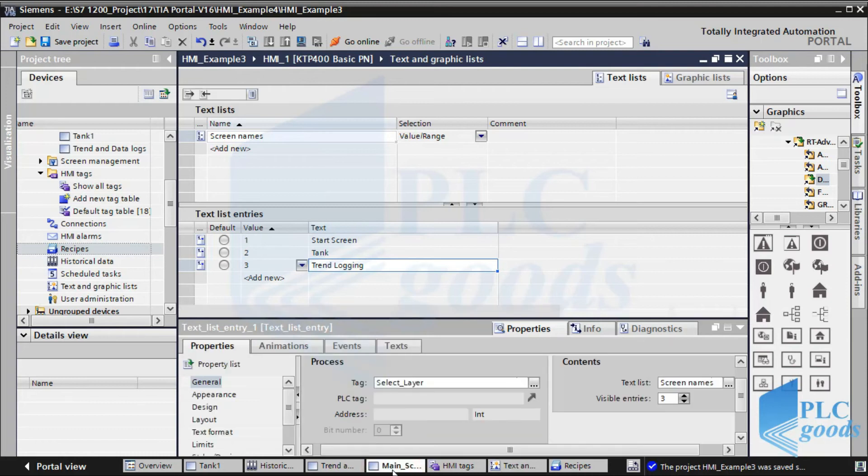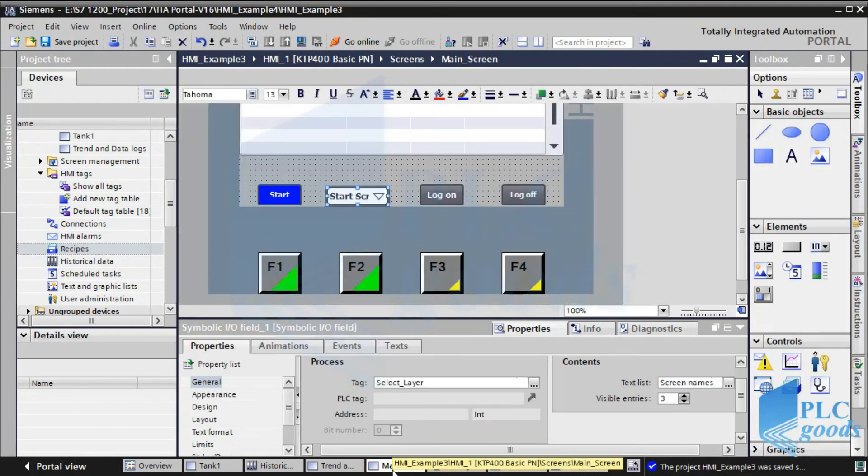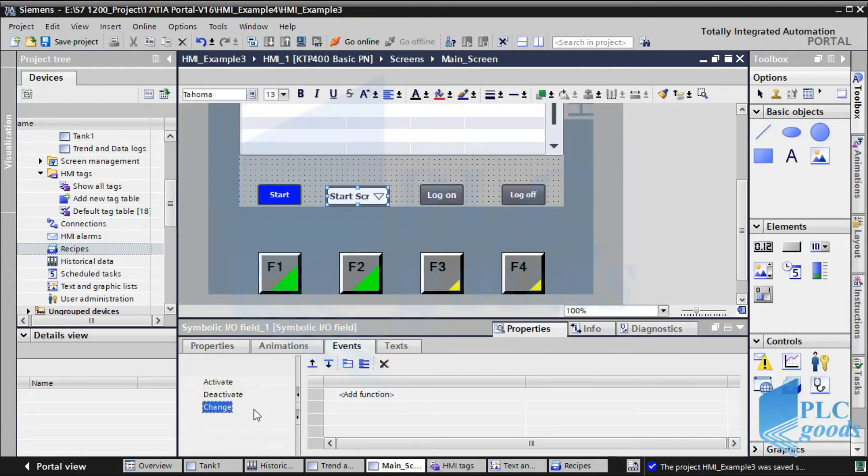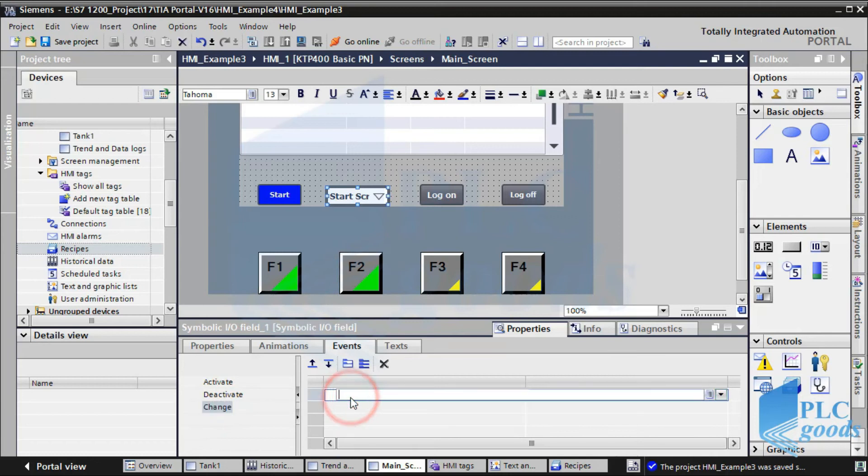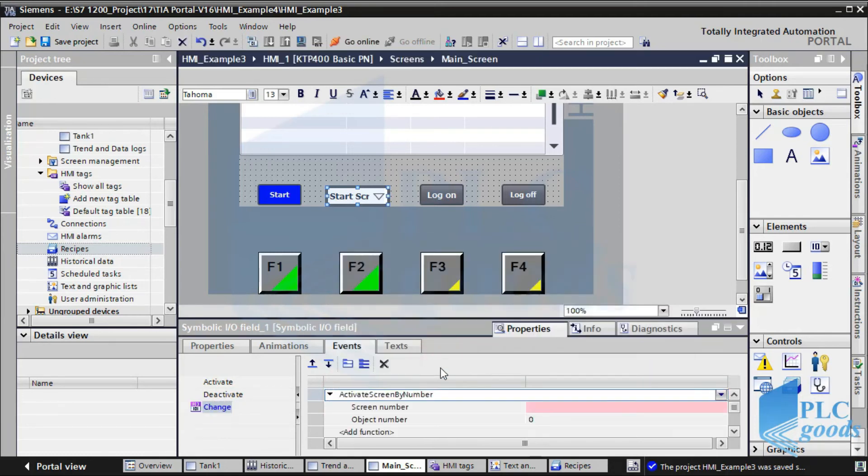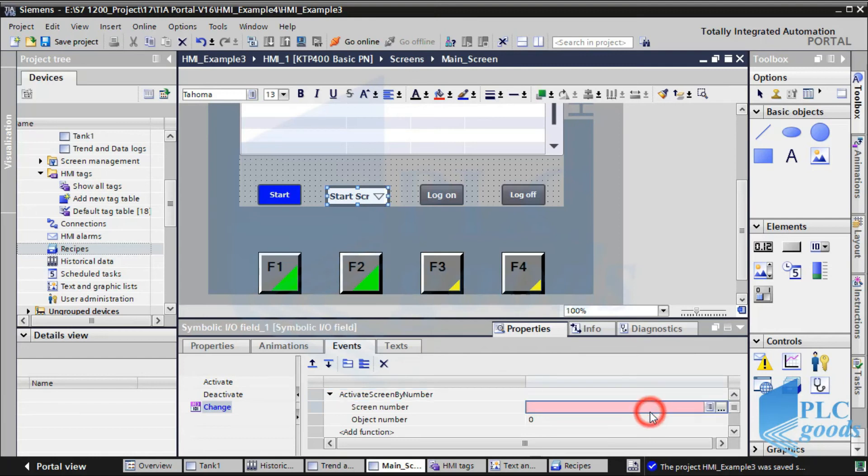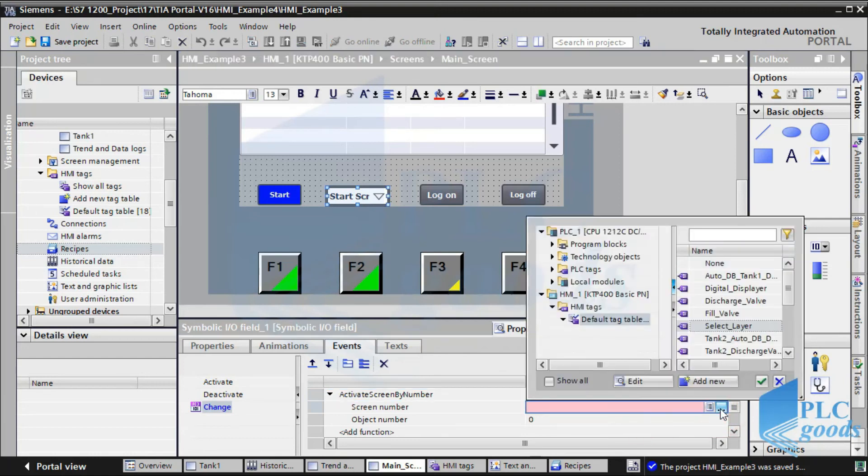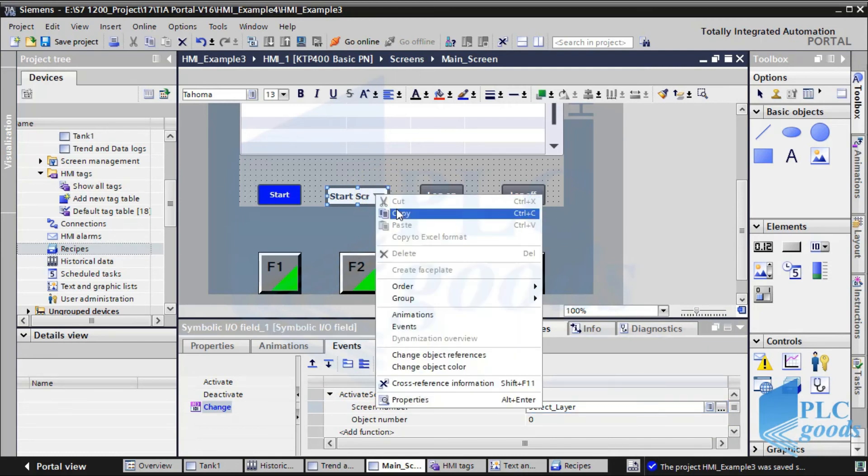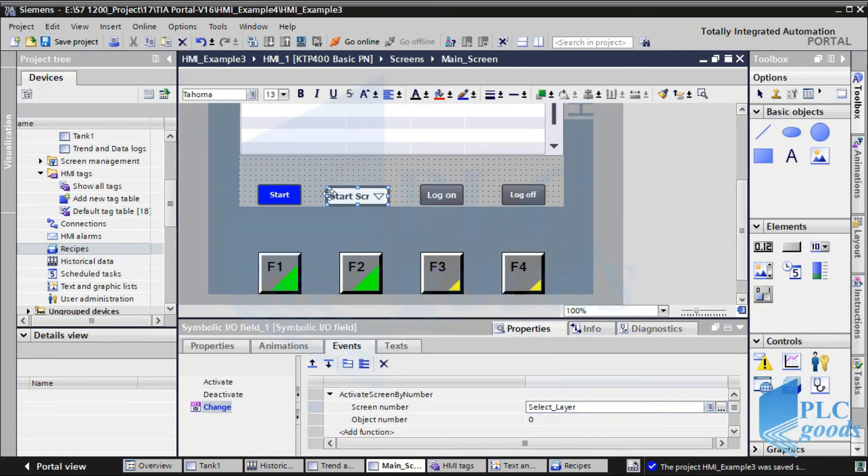Now, in the event tab of the inserted IO field, select change, and then select this function: activate screen by number. Now, connect this function to the defined internal tag. Let's copy this IO field in other screens.